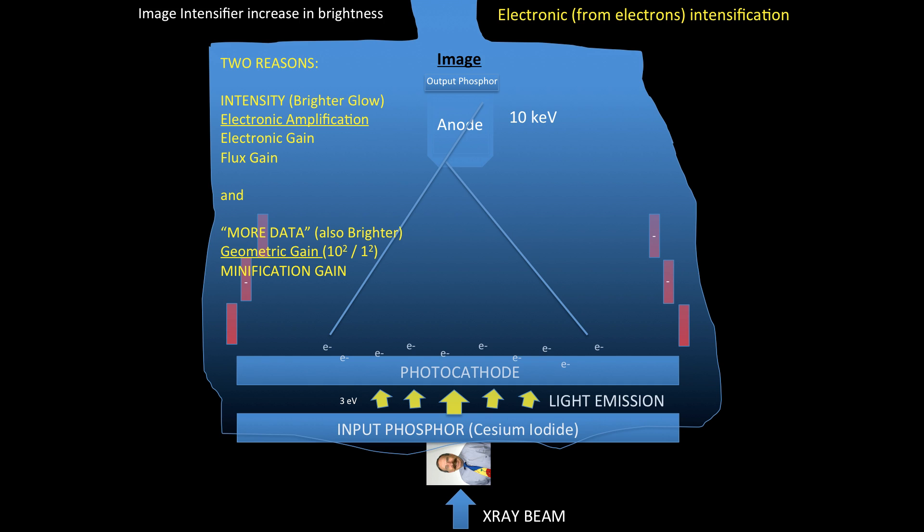And then you have the second component, that's more data. What I mean by that is that you have the data from the input phosphor, which let's say we have a 10 inch input phosphor. Then that's displayed at our output phosphor, which can be a 1 inch output phosphor. And that creates the effect that we have the same amount of data now in a smaller space, and that creates that minification gain or that increase in brightness.